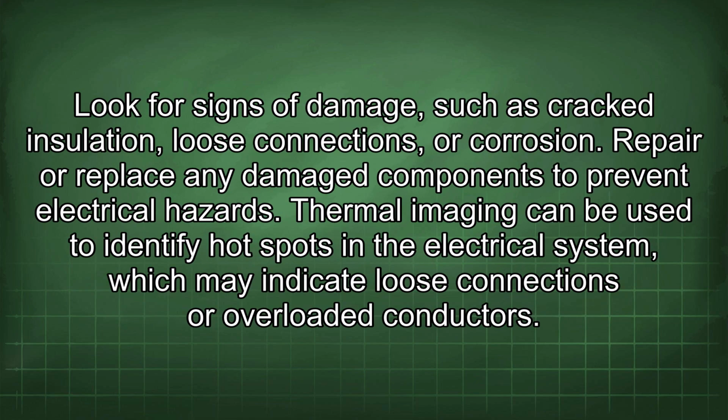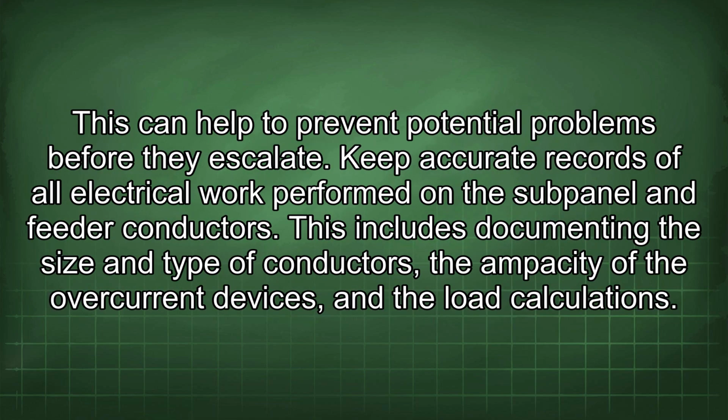Look for signs of damage, such as cracked insulation, loose connections, or corrosion. Repair or replace any damaged components to prevent electrical hazards. Thermal imaging can be used to identify hot spots in the electrical system, which may indicate loose connections or overloaded conductors. This can help to prevent potential problems before they escalate.